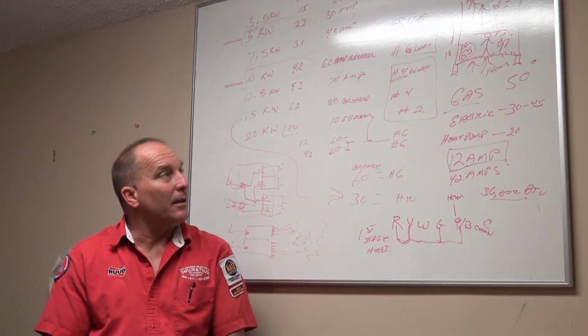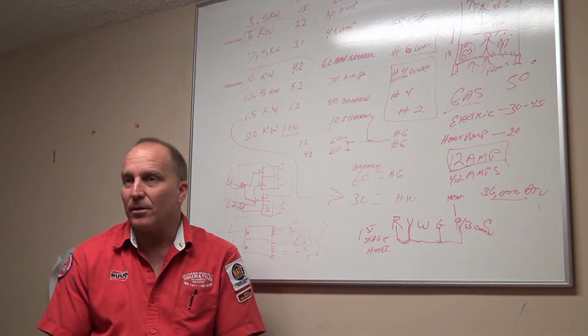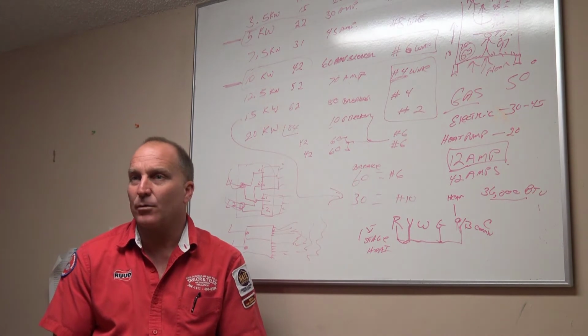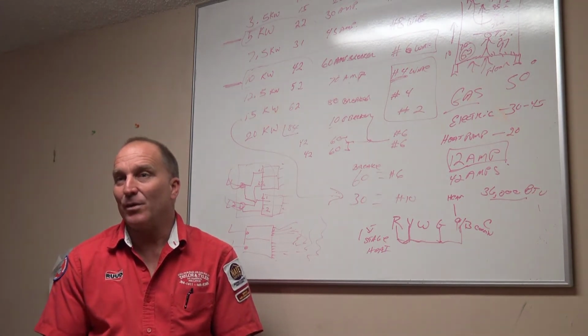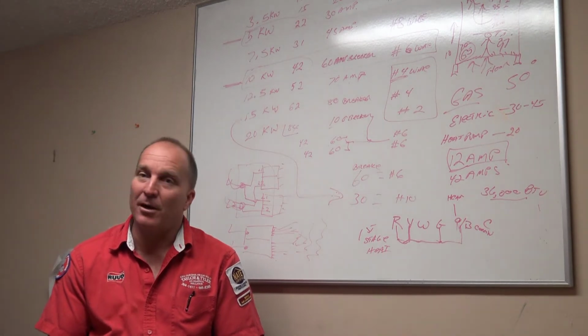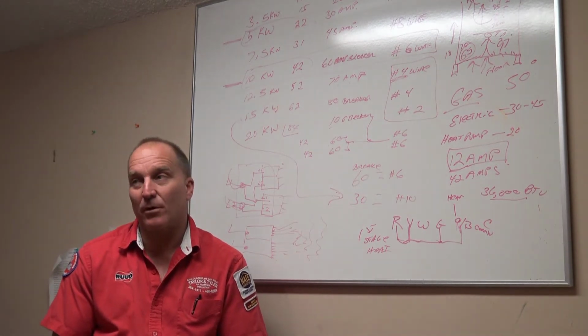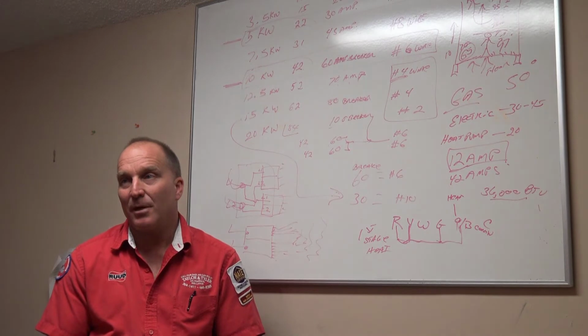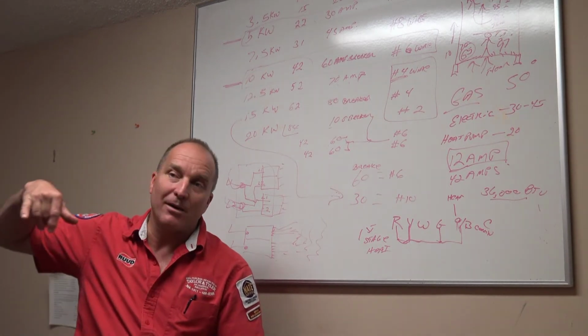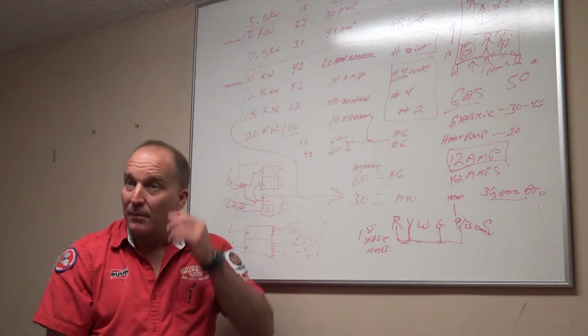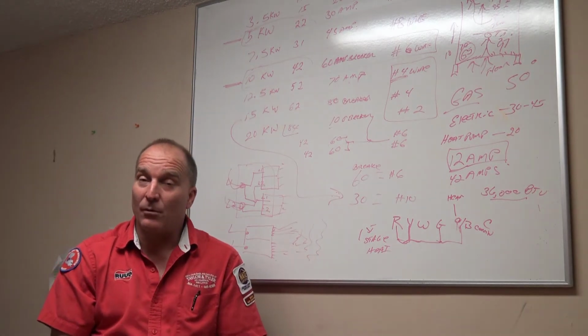So you just gotta heat the home. If you got a slab house, you're good. If you got an above ground New Orleans house with 12-foot ceilings, no, you need gas heat, and you need it on high fan. You need maybe a 100,000 BTU heater on that 3-ton furnace, not a 75, because you got 14-foot ceilings and you need that airflow blowing down. Or you need a floor furnace, right? And get waffle feet.